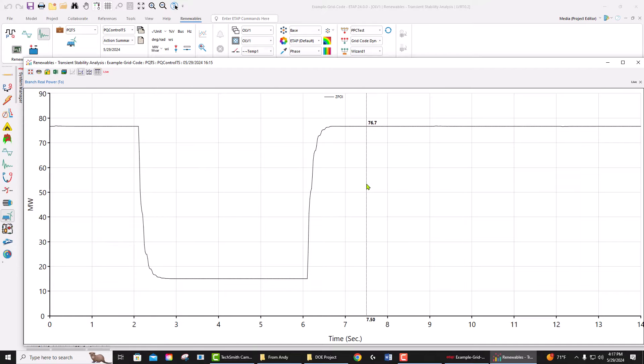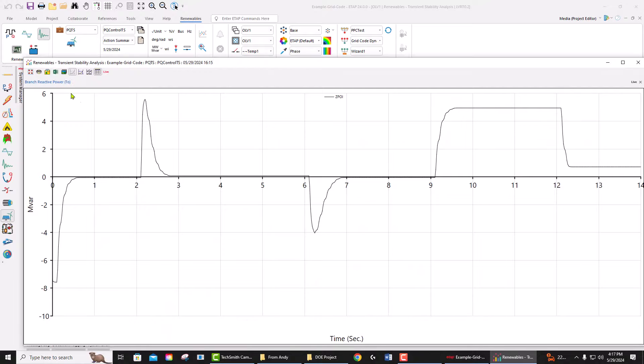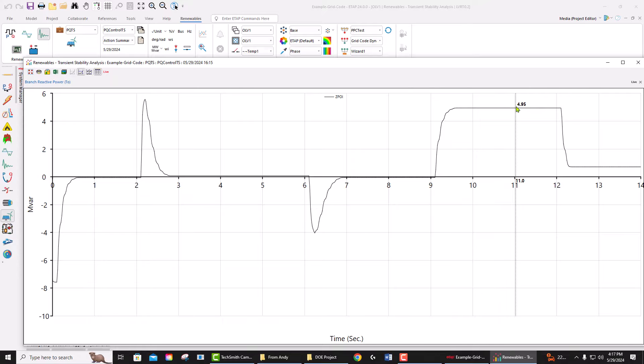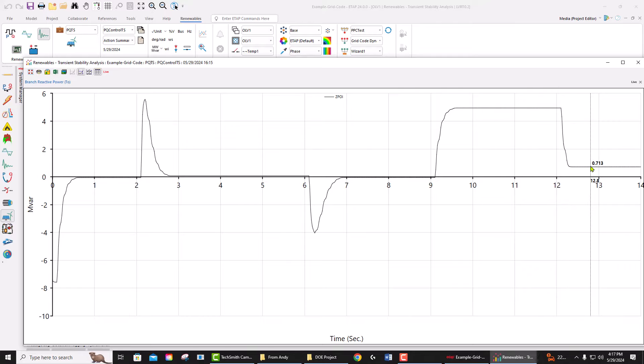of interconnection or point of measurement, you see that at the place where we send a command at nine seconds to go to five megavars, it went to five megavars. Later on, we send a command at 12 seconds to go to power factor mode 100, which means it brings the Q to almost zero. If we go to the display option at the end of the simulation...